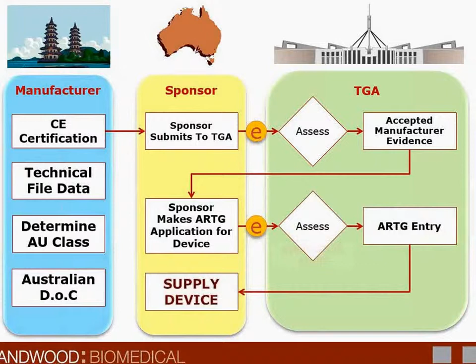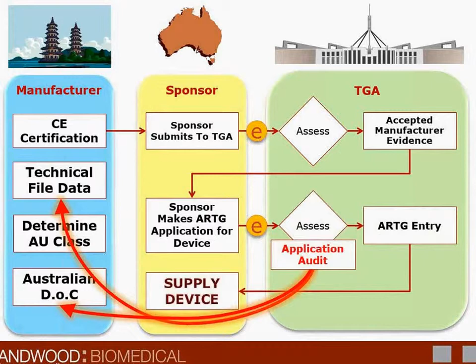What can happen at the time of assessment is the TGA may conduct an application audit, as previously described, where they will write back to the sponsor and request technical file data and the declaration of conformity in order to make a determination as to the acceptability of the devices for supply. Now, the assumption is made at the time of the application that the manufacturer already holds the data, and the application audit comes with a formal request from TGA for information with quite a tight timeline. You have 20 days usually to provide the information, and there are no exceptions and no extensions normally granted. In other words, you cannot go off and start to generate documentation on receipt of the application audit. You're expected to hold it all in advance.